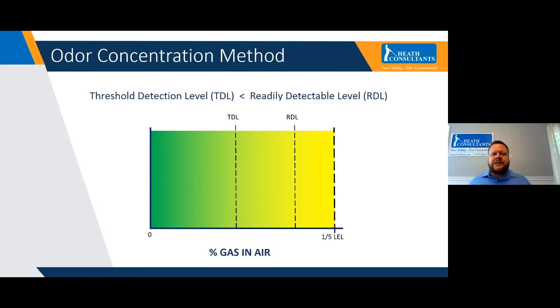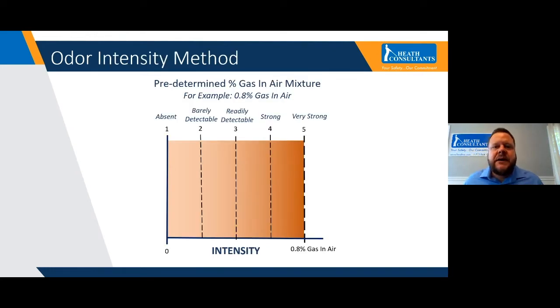And what's important about this odor concentration method is that you want to detect the RDL, or the readily detectable level, below the 1/5 LEL limit. So somewhere usually between 0.75 and 1% gas is usually what most operators dictate, but you want it to fall somewhere below 1% gas in most cases. Now, the second method that we discussed is the odor intensity method. And the Odorator 2 is capable of performing both of these types of tests.